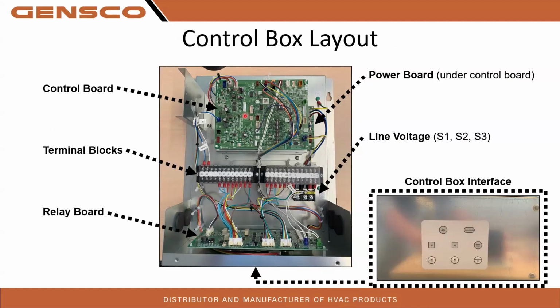control board here. Behind that is a power board, TBA terminal block, TBB terminal block. So TBA is for your furnace equipment, TBB is for your thermostat. And I'll get more into that here in a bit. Right here you have your TB3 terminal block, which is your S1, S2, S3 that I'm sure we're all familiar with. So that's what the communication is between your coil and your heat pump or your branch box.